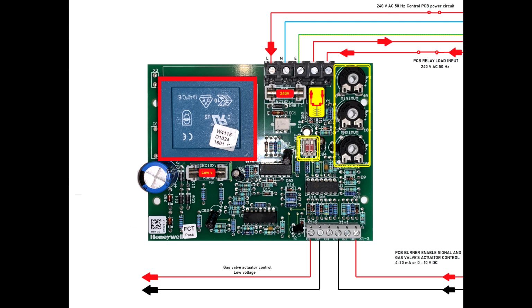You will set up the dead band in which this boiler will run. You will set up the minimum voltage at which this printed circuit board will enable the burner via that relay, which is marked with yellow, where you'll see the signal coming in and going out.